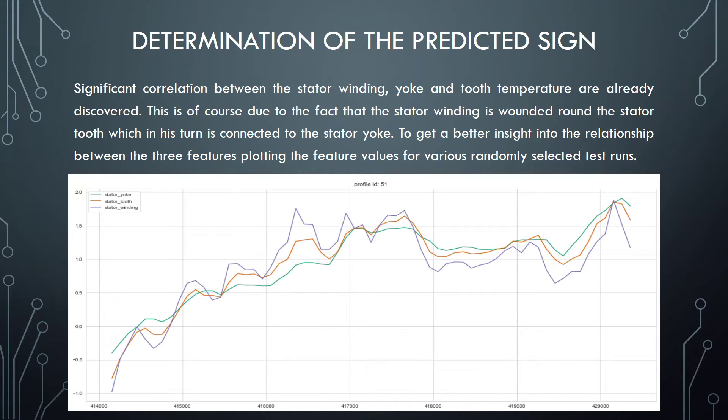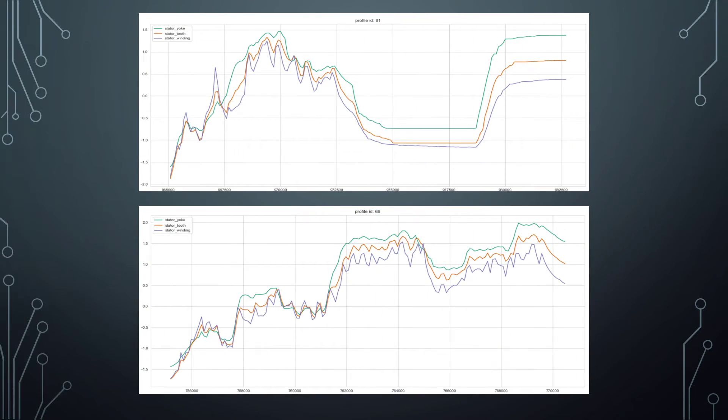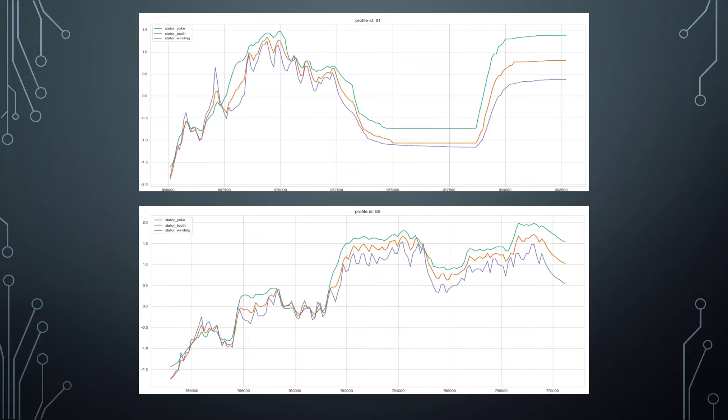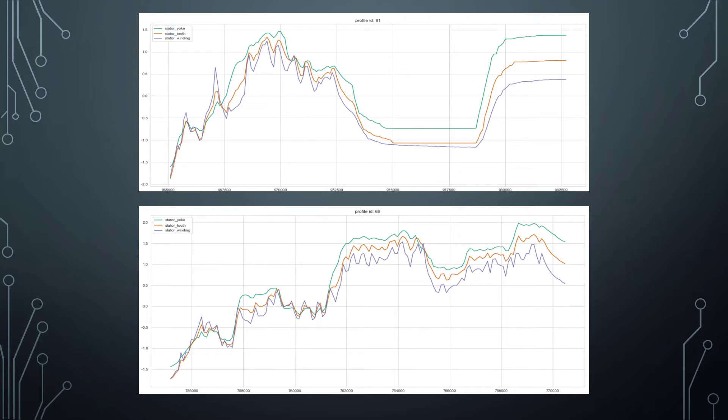On this slide you can see the test run profile ID. On the next slide you can see test runs 81 and 69. The line plots confirm that all three temperatures follow the same trend. The stator winding temperature shows the biggest variation followed by the stator tooth and stator yoke temperature. This is especially noticeable when there is a lot of variation in the stator winding temperature. The stator tooth and yoke temperatures follow a smoother path than the temperature recorded on the stator winding. In other words, the heat dissipated by the stator windings takes some time to heat up the stator tooth and yoke due to the thermal inertia of both stator parts.